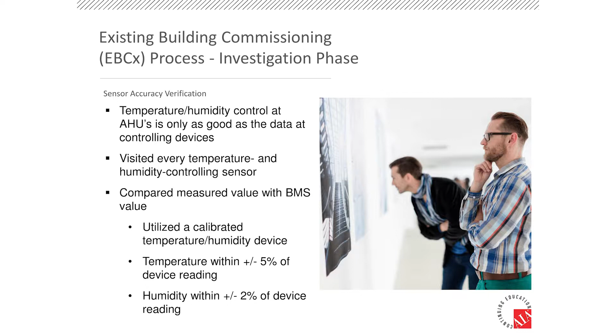So what we did, which was very successful actually, was go to every single controlling device in terms of temperature and humidity, and put our own calibrated test gauge next to that device and say, okay, I'm showing a temperature of 72 degrees. Mr. BMS man, what is my temperature saying at the BMS front end? Oh, well, it's saying 63. Okay, so that's a huge spread. Now we understand why some of the control is not right. It thinks that it needs to heat, for example. It's trying to get to 72, but we're already there, so we're overheating, in fact.